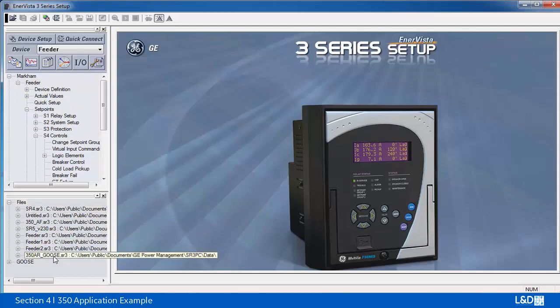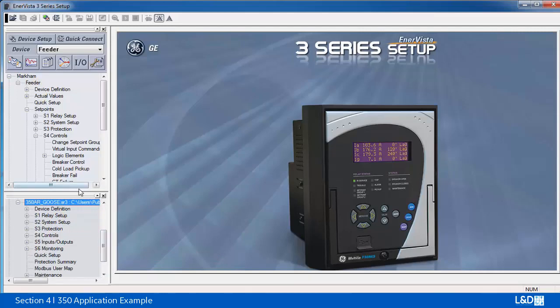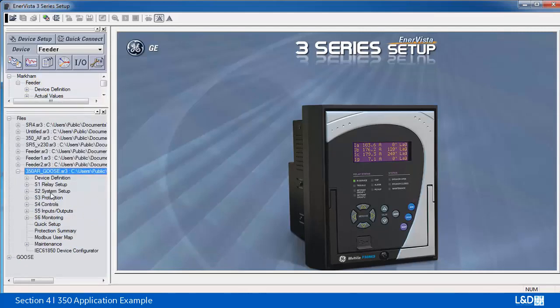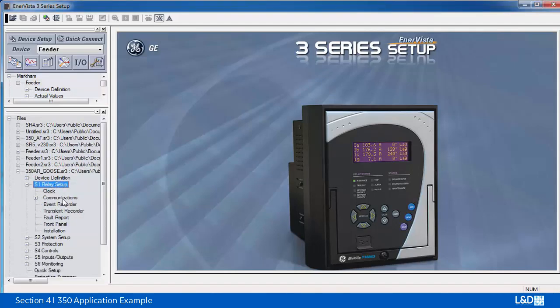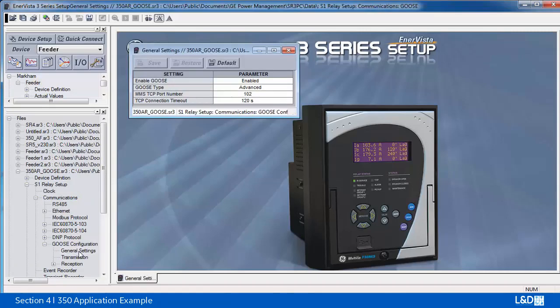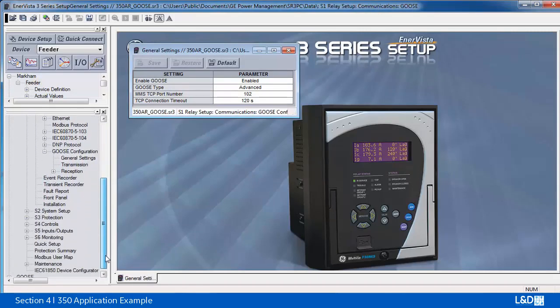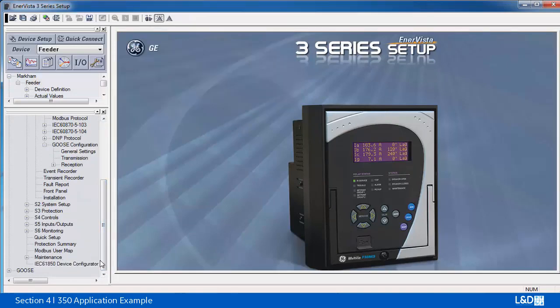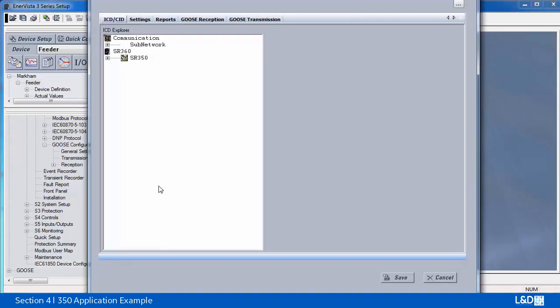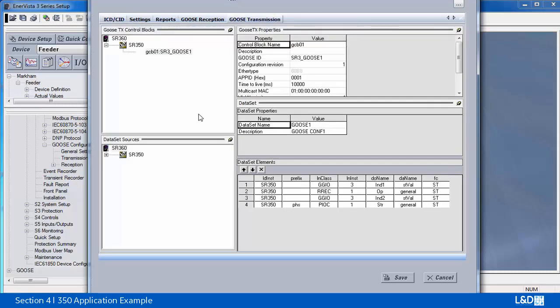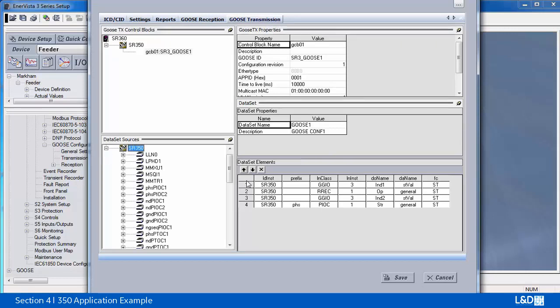So we have one offline setting file, 350 AR goose. We need to first make sure that the communication is in the advanced mode, and then under the 61850 configurator, we're going to publish 4 outputs. So that's under transmission, and these are the 4 outputs we drag and drop from the GGIO3. That's the virtual input 1, which will be used for the manual close of the breaker.